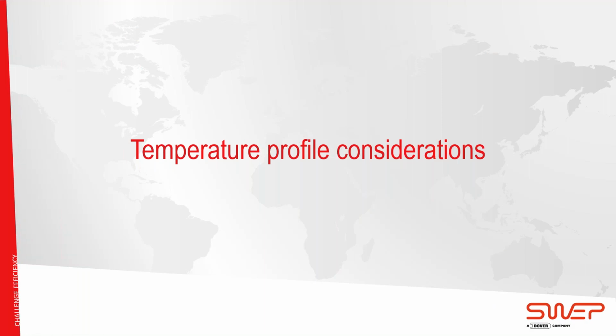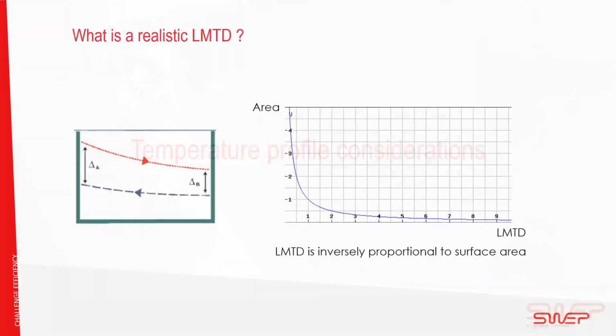So now some temperature profile considerations. What is a realistic LMTD? The required temperature difference between the two fluids, as shown on the left here, is called the logarithmic mean temperature difference, or LMTD, and this has a direct impact on the size of the heat exchanger. The relationship between LMTD and area is inversely proportional, and so a decrease in LMTD leads to an increase in the required surface area, and hence the physical size and also cost of the heat exchanger.